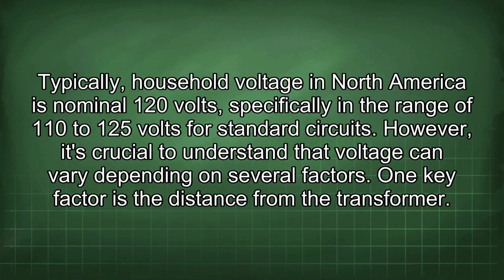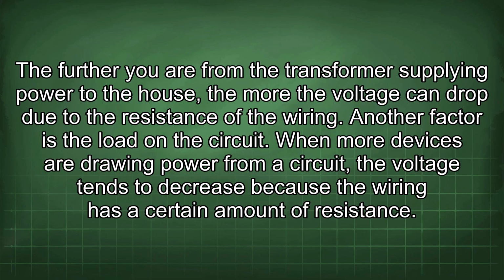Typically, household voltage in North America is nominal 120 volts, specifically in the range of 110 to 125 volts for standard circuits. However, it's crucial to understand that voltage can vary depending on several factors. One key factor is the distance from the transformer. The further you are from the transformer supplying power to the house, the more the voltage can drop due to the resistance of the wiring.